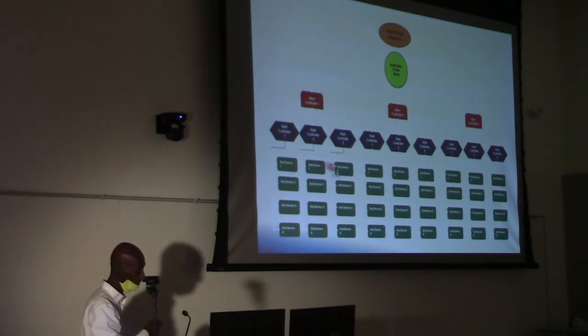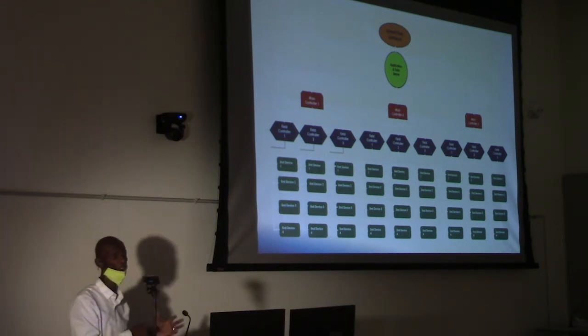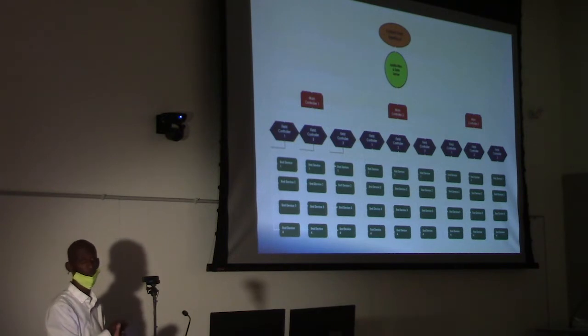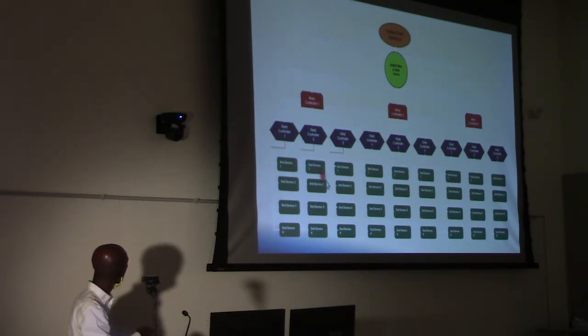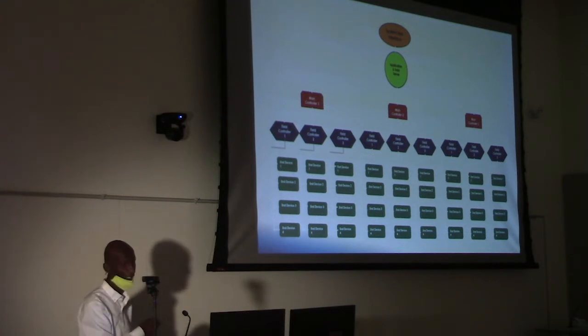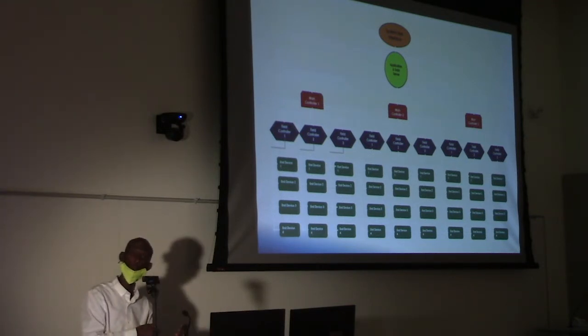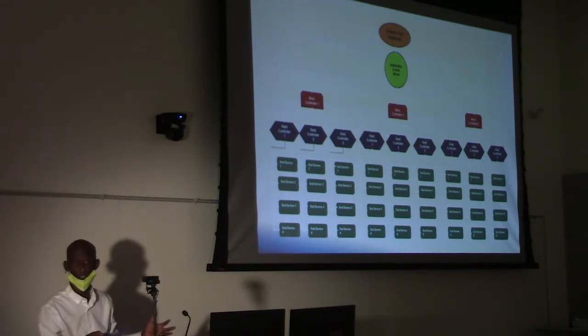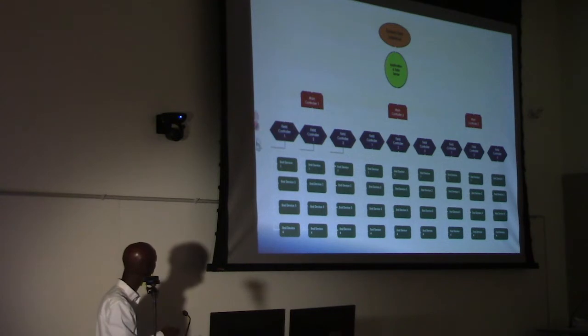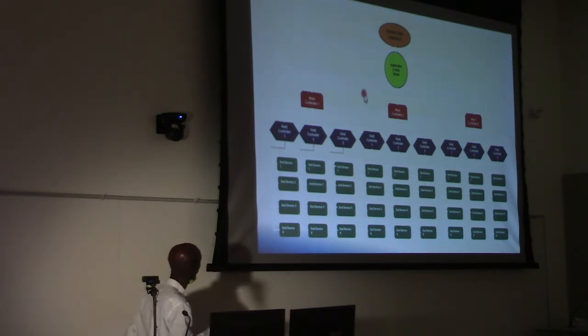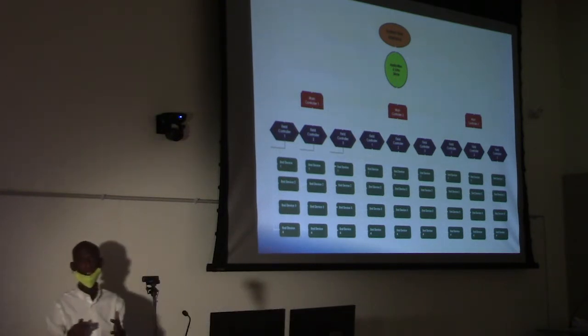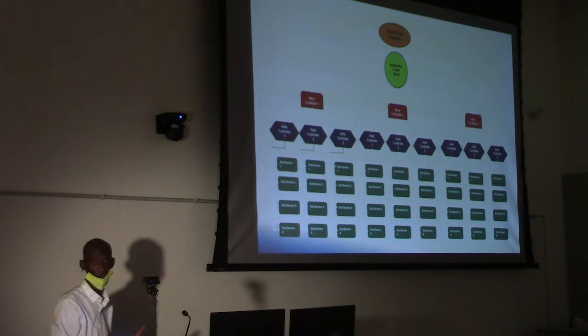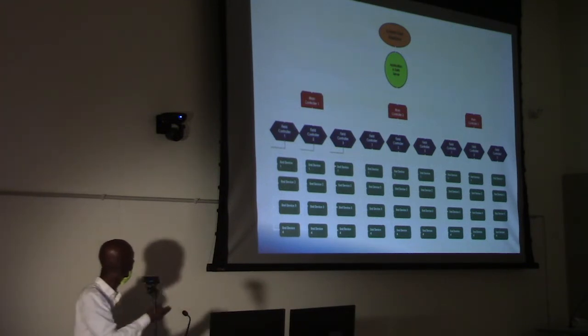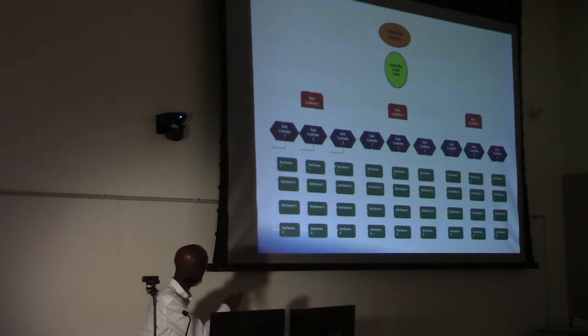report to a main controller. The main controller is large. It can have between 2,500 points to 5,000 points. So these field controllers dump all the information into a main controller. And the main controllers, you can have 1 or 2 per building, depending on the number of points you have in a building, and depending on the size of the building or the size of the equipment. And then the main controllers report to an application and data server. Here on campus, we have 1 large data server that helps us control all the main controllers on campus. And then you access it through a user interface system.